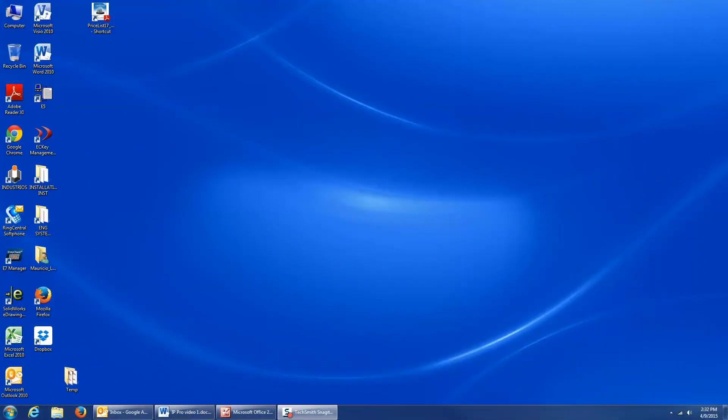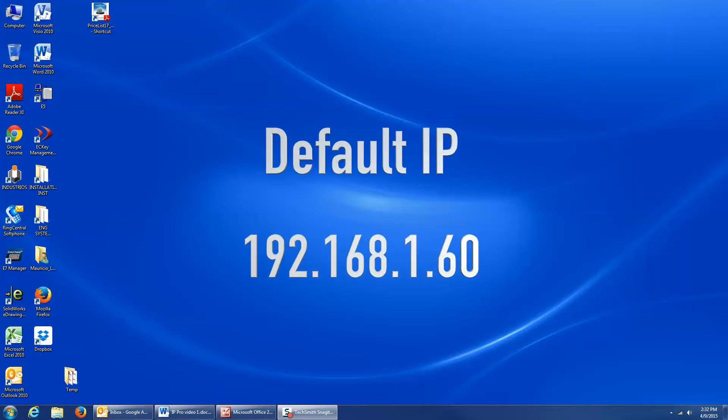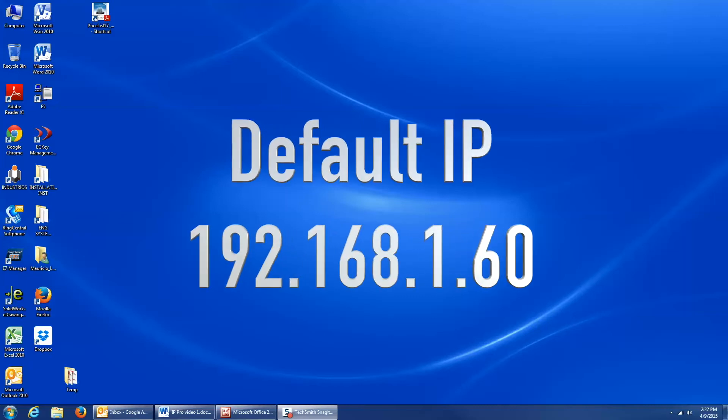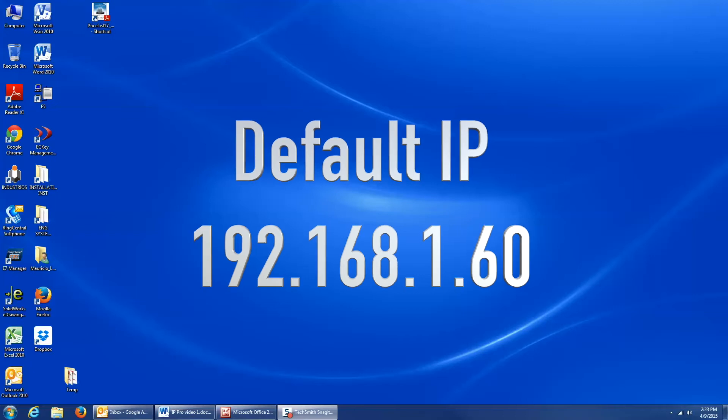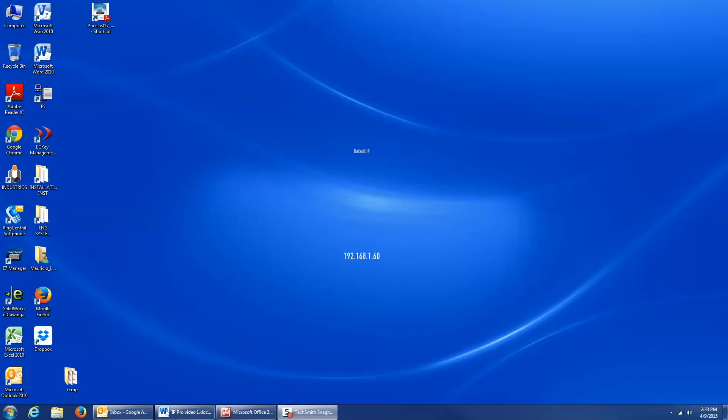I will now be demonstrating how to establish communication with the IP-PRO controller when a PC or laptop is connected directly to the controller's Ethernet jack. Out of the box, the controller is configured to use the default static IP address of 192.168.1.60, so I want to change my computer's static IP address to be on the same subnet as the controller. This process is also detailed in the IP-PRO installation manual.